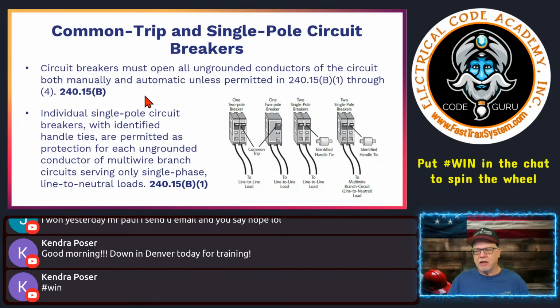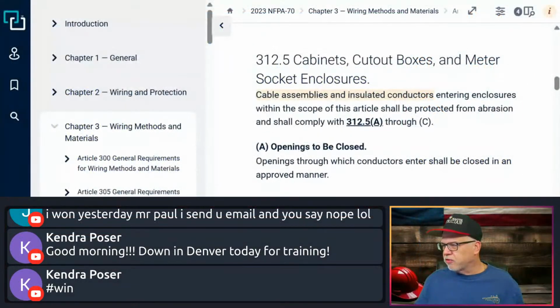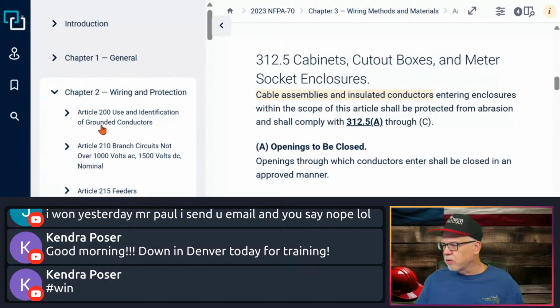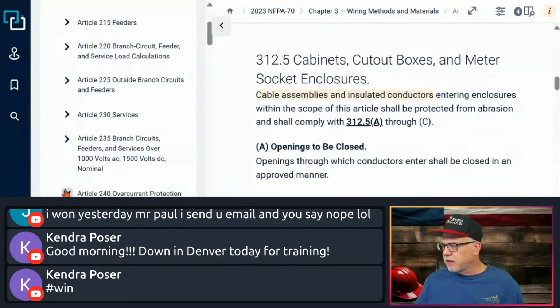So circuit breakers, especially if you're going to use something like a multi-wire branch circuit, it's so important that you disconnect. If you're doing a multi-wire, you're going to have two phases sharing a neutral. You want to make sure that they simultaneously disconnect, right? All right, so circuit breakers must open all ungrounded conductors of a circuit both manually or automatically unless permitted in 240.15(B)(1) through (B)(4). And that is in 240.15(B). So we're going to look at that and see what it's talking about. And let's see here. So we're talking about just circuit breakers.